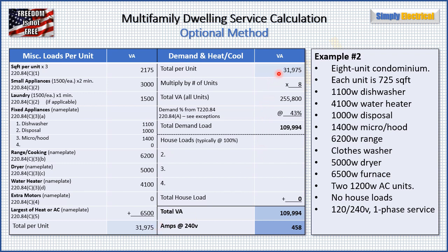Adding all these together, we get 31,975 VA per unit. Slide that number up and multiply by eight units, giving us 255,800 VA total building VA. Table 220.84 tells us that eight units gives us a demand factor of 43%. So 43% of 255,800 is 109,994 VA for our total demand load. No house loads, so 109,994 is our total VA. Divide by 240 single phase, and we get 458 amps for our service size.